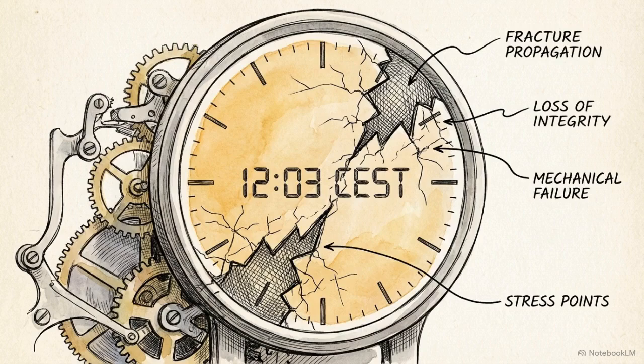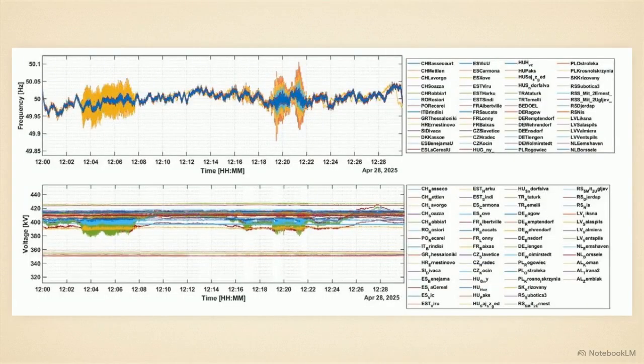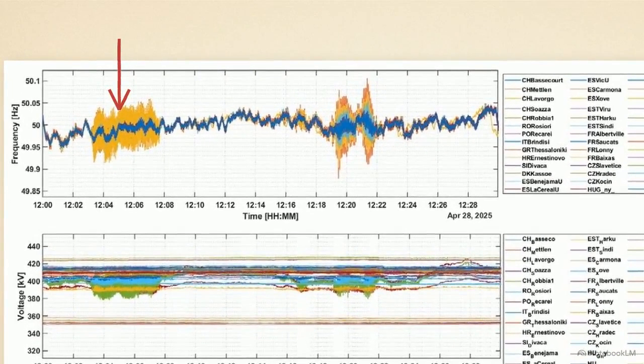Shifting the timeline back to 12:03 CEST, the system recorded an initial grid disturbance. This data comes from phasor measurement units, measuring electrical waves on the grid in real time. The charts show intense signal variance, capturing two distinct oscillatory events echoing across the continental synchronous area. The first event is a 0.63 Hz forced oscillation, localized entirely within the Spanish grid. This oscillation acted as an exciter for a wider event, a 0.2 Hz inter-area mode spreading across the entire European continent.